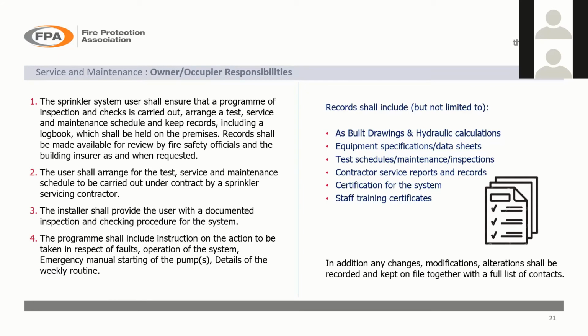There are quite a lot of times we go to site and we find that weekly tests are being carried out, there's evidence that it's been done, but it's not really been done in accordance with the standards. And the reason for that is that it's how we were shown to do it by the last guy who did it. So there's no proper formal training in some instances. So it's important to keep your staff training up to date as well, and keep that in the form of records. So any modifications that you make as well, you need to keep records of that. So ideally, you'll have a set of drawings, a set of certificates, and a set of training certificates as well. So they should all be maintained on site and easy to access.